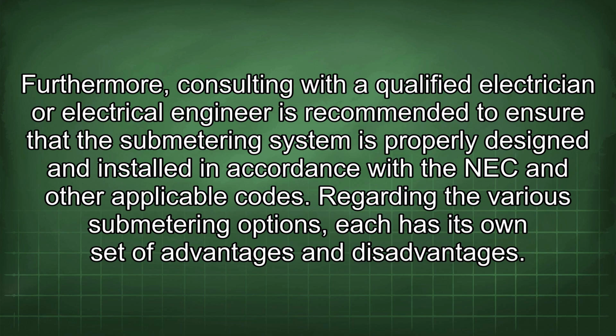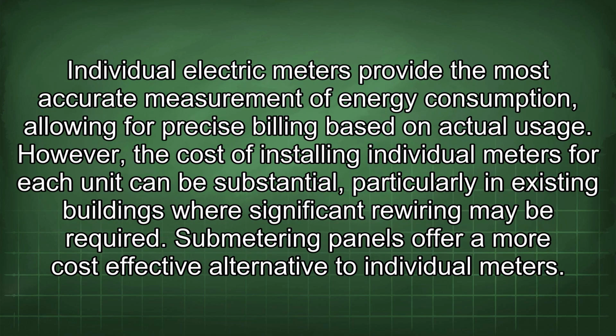Regarding the various submetering options, each has its own set of advantages and disadvantages. Individual electric meters provide the most accurate measurement of energy consumption, allowing for precise billing based on actual usage. However, the cost of installing individual meters for each unit can be substantial, particularly in existing buildings where significant rewiring may be required. Submetering panels offer a more cost-effective alternative to individual meters.